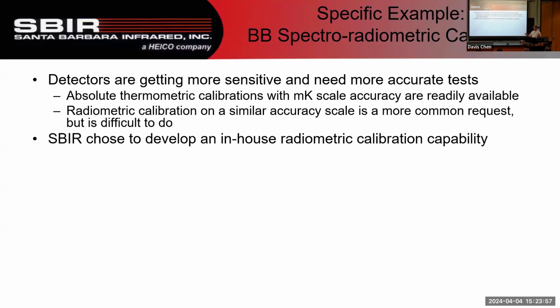What's going on now is people make better and better infrared cameras. As they get more sensitive, people want to do more and more sensitive tests to make sure they're accurate. Absolute thermometric calibration with millikelvin scale accuracy is pretty simple. It's not too hard to do a thermometric measurement with probes, or you can get SPRTs or thermistors that are accurate to a few millikelvin, absolute, without too much trouble.